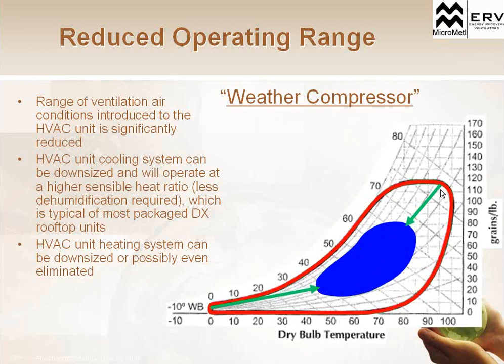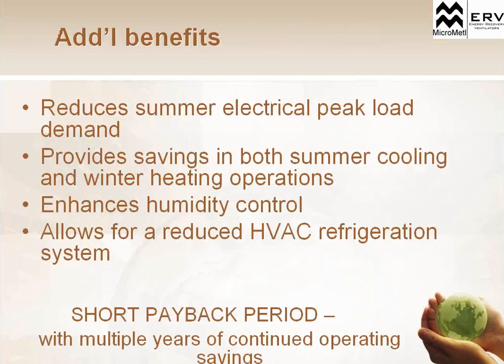So now we no longer have to size our rooftop unit for these peaks up here, the temperature and humidity peaks or lows. We can size our rooftop unit to just handle the small blue bubble, reducing the amount of capacity we have to have available. So the HVAC system itself can be downsized to what we would normally typically size for. If we look at some of the additional benefits, because we're reducing the amount of energy required by the heating and ventilation unit to heat and cool that outside air, we're going to reduce the electrical load during peak demand hours.